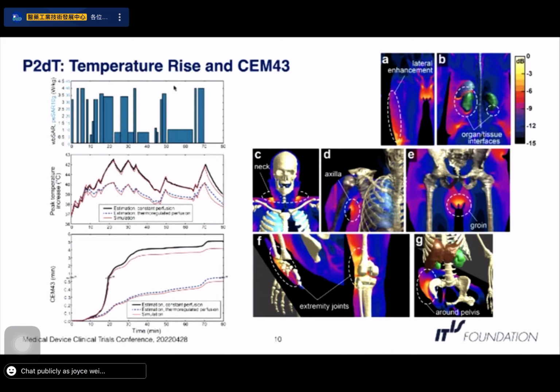And on the left here, you can see a graph that shows over time the peak spatial SAR or the whole body SAR, doing an MR scan that's 70 minutes long, for example, and the peak temperature increase compared to that. But this needs to be translated into this factor that's called thermal dose, or CEM43, where we hit the point, or already after 20 minutes for some cases, depending on the perfusion model, where there's actually damage caused to the tissue. So these are all factors that need to be considered in the modeling process for the power to temperature conversion.